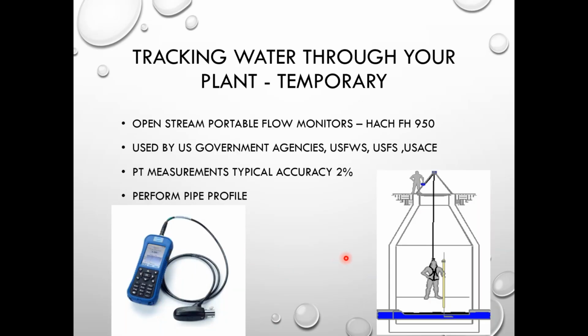So how do we do this in open channel? Well, we do this with portable velocity meters, and this one actually has level as well. So this is a flow meter that you can get from Hach. It's what we call an FH950. They're very popular for being used for stream monitoring with U.S. Fish and Wildlife Service, U.S. Forest Service, Army Corps of Engineers, and any type of large open channel system. This sensor is a great device to go out and do what we call velocity profiling of streams and creeks. It's a point measurement.